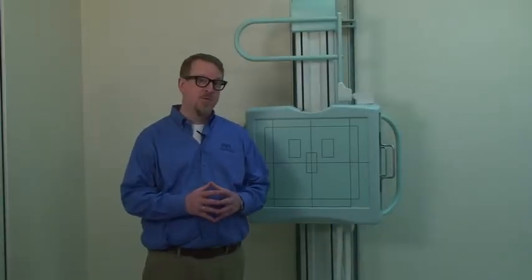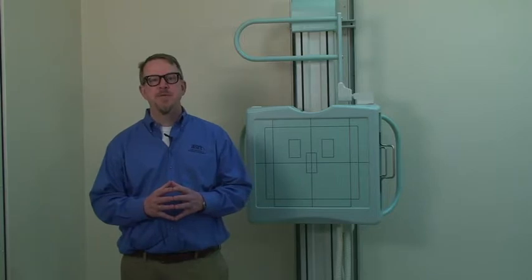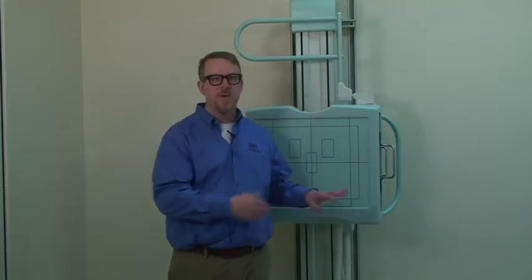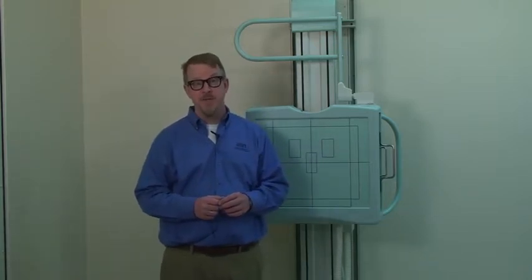Radiation protection is built into any room designated for use with radiation equipment. Two types of barriers, primary and secondary, coincide with protection from either the primary beam or secondary scatter. The primary beam is the photon energy directed from the X-ray tube through a patient to an image receptor. The primary beam is given the most consideration because it contains the highest amount of radiation.